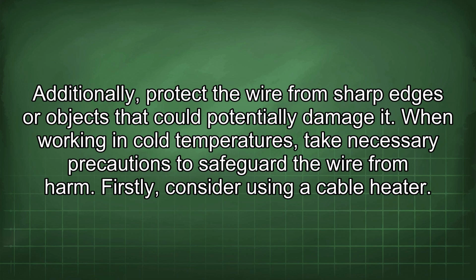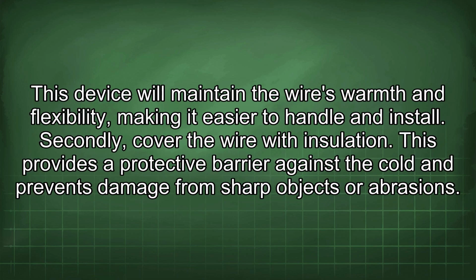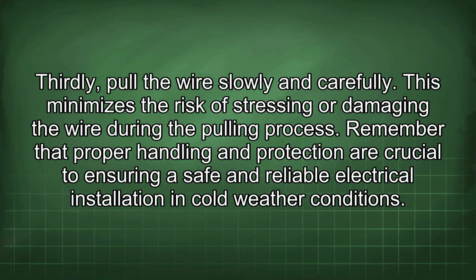Firstly, consider using a cable heater. This device will maintain the wire's warmth and flexibility, making it easier to handle and install. Secondly, cover the wire with insulation. This provides a protective barrier against the cold and prevents damage from sharp objects or abrasions. Thirdly, pull the wire slowly and carefully. This minimizes the risk of stressing or damaging the wire during the pulling process.